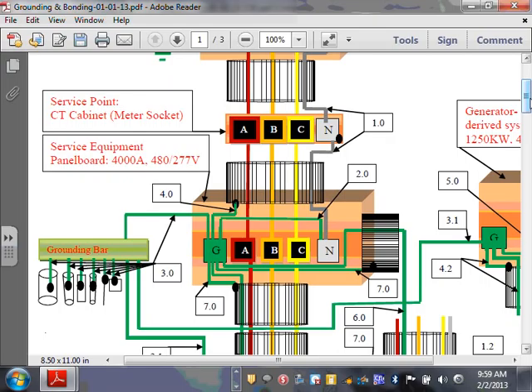The first thing you do there is number 2. Number 2 is called the main bonding jumper. Cool? Everybody understand that one? Number 2 here is a piece of copper or aluminum, or it could be a copper bar inside your switch gear, and you bond your neutral to the grounding bar. In turn, the neutral will be bonded to this ground bar, and the ground bar is bonded to the frame. So the ground bar will be directly bonded to the frame of the switch gear.